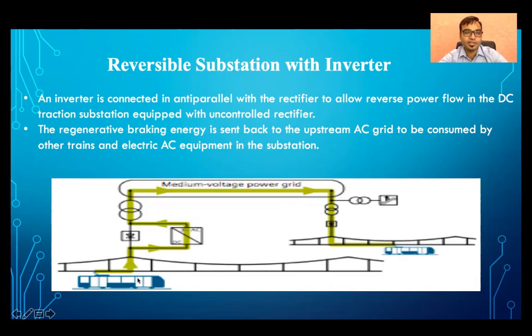When the train is regenerating, the regenerative power flows from the DC network to the inverter, which converts the DC energy into AC energy, and it is fed back through a transformer or auto transformer to the medium voltage network. This energy can then be utilized in auxiliary systems, or it is further converted back to DC using rectifiers and fed to another train anywhere in the section.